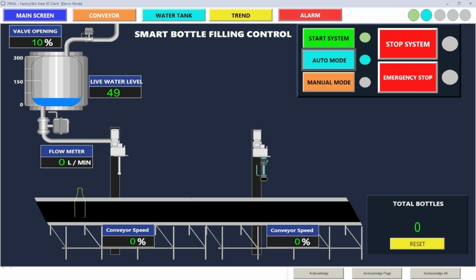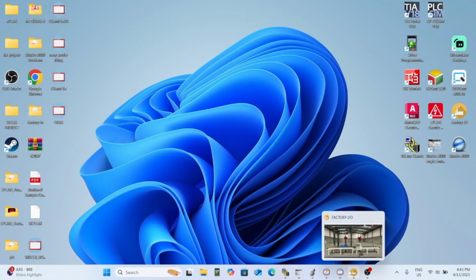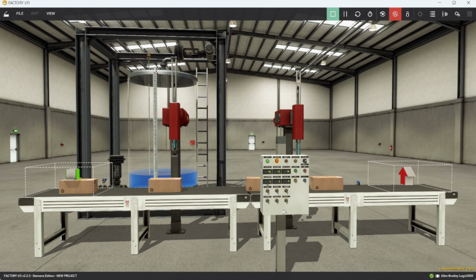It's a neat layout with intuitive navigation. The header shows system status, active alarms, and a blinking indicator to show whether the process is running. I've used a custom color palette, avoiding blue since it's already used for the water tank, to make it visually clear and pleasing. There are start, stop, and emergency stop buttons. When you press the emergency stop, the system latches off and a blinking reset button appears. This can only be used once the emergency is cleared, adding a realistic safety interlock.